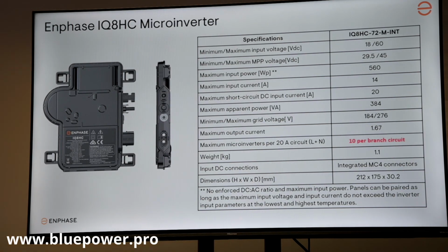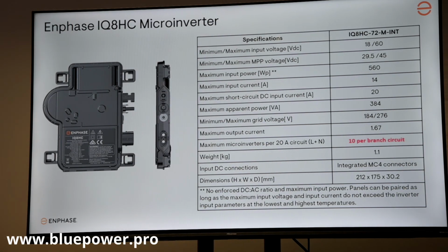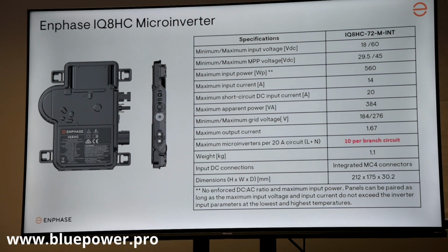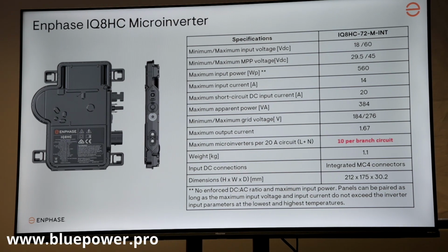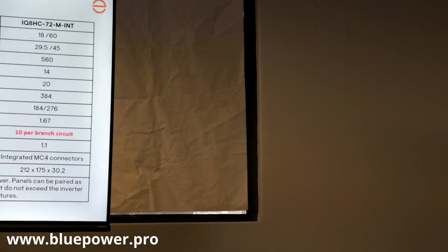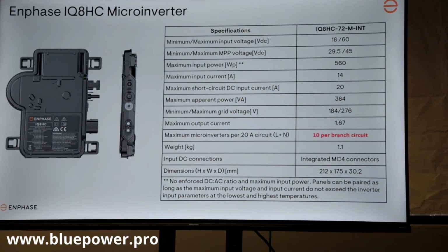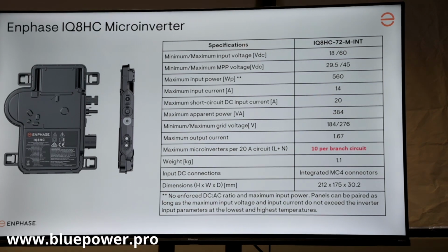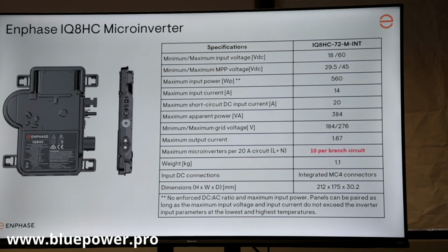Looking at the Enphase IQ8HC microinverter, because of the components that make up the system, we can put 10 of them on a branch circuit. When I say branch circuit, it's this cable used for the microinverters. On the IQ8HC, you can go up to a maximum of 10 on one of those cables, because of the relay's rating of 25 amps.